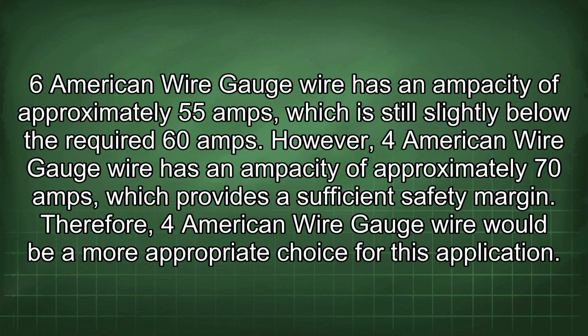necessary. 6 American wire gauge wire has an ampacity of approximately 55 amps, which is still slightly below the required 60 amps. However, 4 American wire gauge wire has an ampacity of approximately 70 amps, which provides a sufficient safety margin. Therefore, 4 American wire gauge wire would be a more appropriate choice for this application.